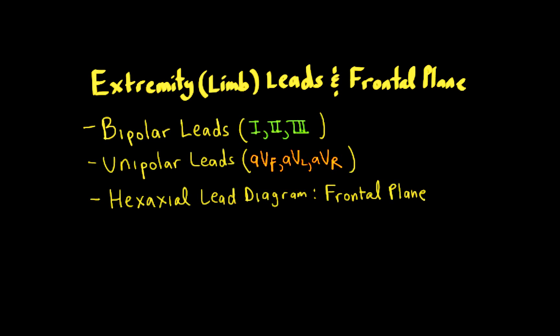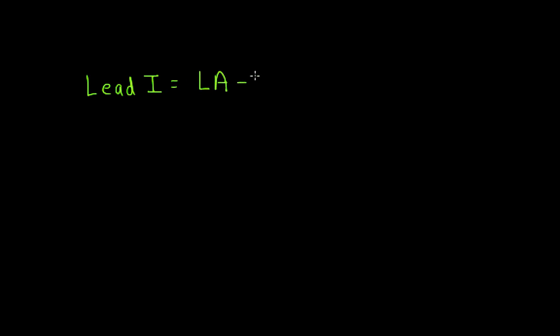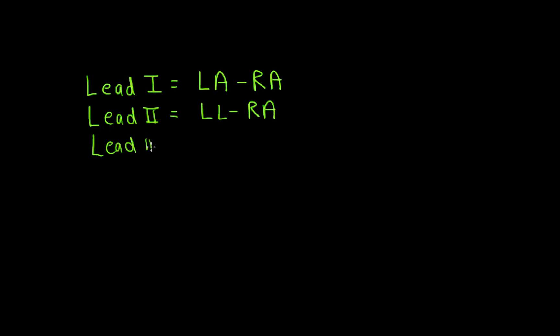Let's start with the bipolar leads. They have this name because they record the differences in electrical voltage between two limb electrodes. Lead 1 records the difference in voltage between the left arm electrode and the right arm electrode. Lead 2 records the difference between the left leg electrode and the right arm electrode. Lead 3 records the difference between the left leg electrode and the left arm electrode. Inside the electrocardiograph machine, these subtractions are done.